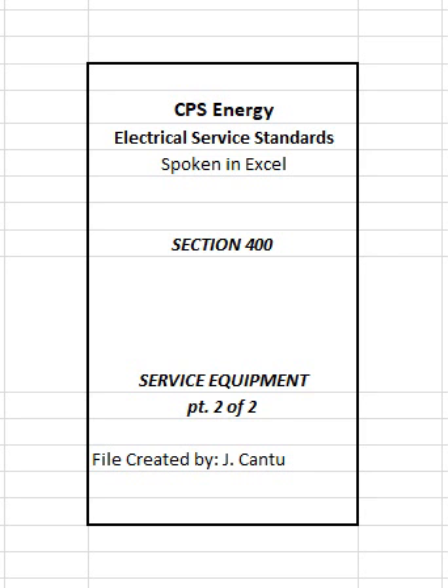405.2 Height of operating handles. The grip center of the service disconnecting means operating handle shall not be more than 6 feet 7 inches above floor or working platform. 405.3 Remote control. Where a remote control device is used to actuate the service disconnecting means, the service disconnecting means shall be required to be located in accordance with the provisions of the NEC and applicable codes including this section.